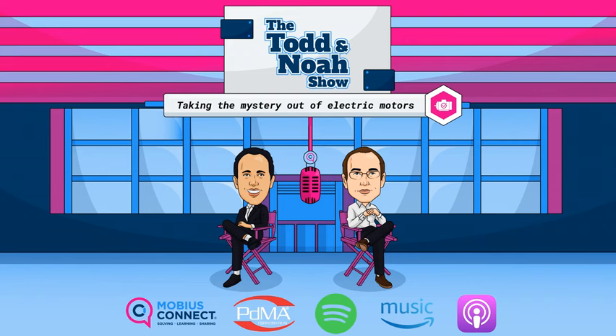Can I tell you this? The inrush startup test, as you're describing, is capturing current and voltage at the start of a motor. And that's important. It is my favorite test of all tests. There are all kinds of electrical tests you can run, but that inrush startup test is so telling. It's the most stressful time of a across-the-line motor start. If you can actually watch what that motor goes through during this very stressful moment of its life, it tells a lot about the motor.